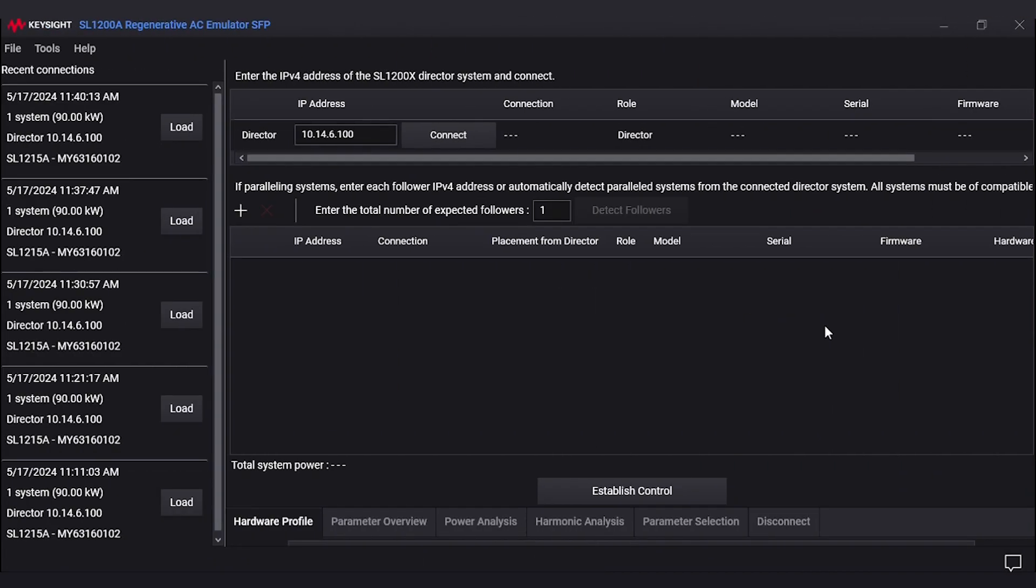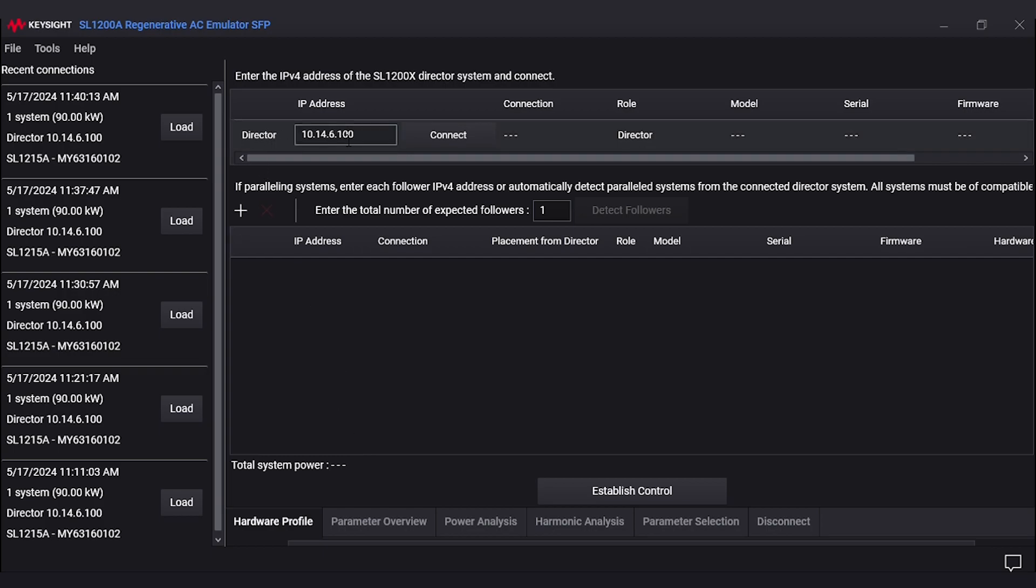Here is the software for the SL1215A. This is how you control the AC grid simulator. First thing you want to verify is that the director's IP address is set correctly. As you can see, our IP address is 10.14.6.100. We're going to hit connect to tell the software to connect to the instrument.